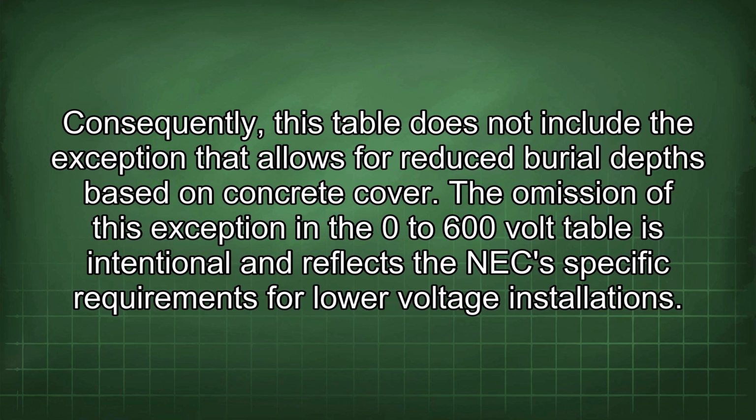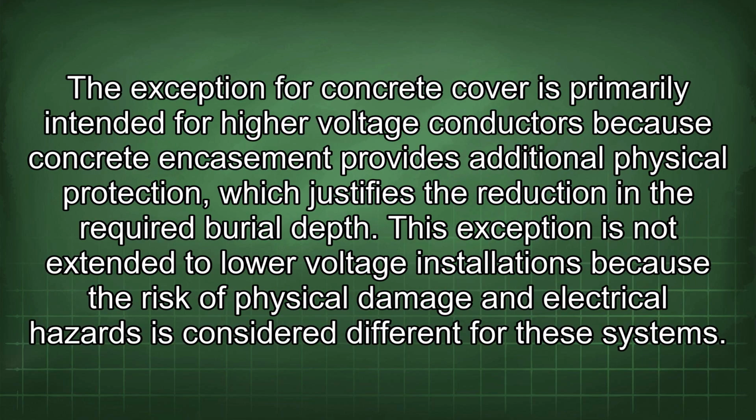The omission of this exception in the 0 to 600 volt table is intentional and reflects the NEC specific requirements for low voltage installations. The exception for concrete cover is primarily intended for higher voltage conductors because concrete encasement provides additional physical protection, which justifies the reduction in the required burial depth.